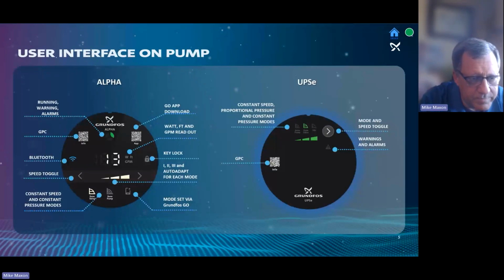So looking at what we call the foil, the faceplate, the top of the pump. The UPSe does have a button. It's not the touch screen, it's a button. And with this one, when you touch this button, it'll toggle through the 3 different settings for the constant curve, 3 different settings for the constant pressure, and then for the proportional pressure. You barely see it down here.